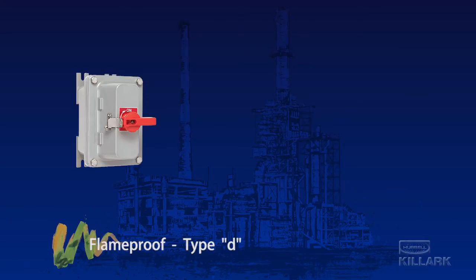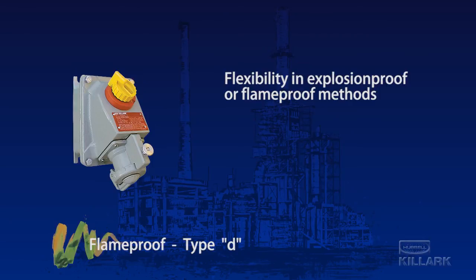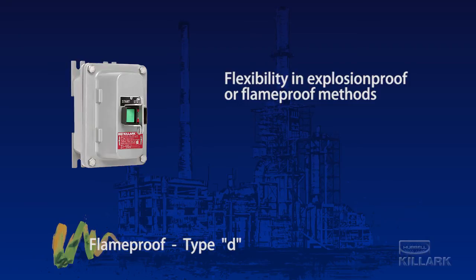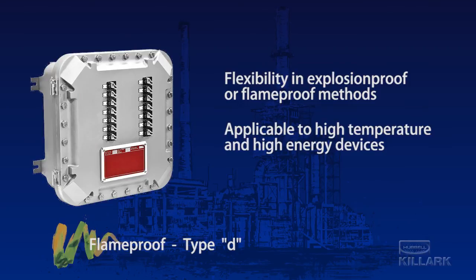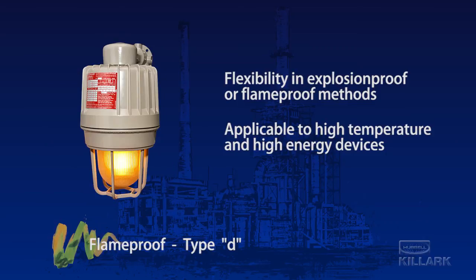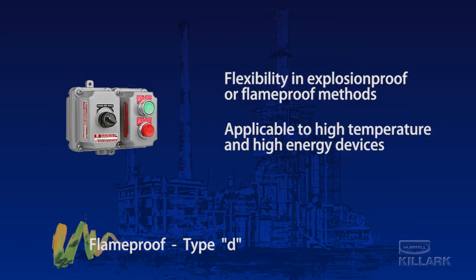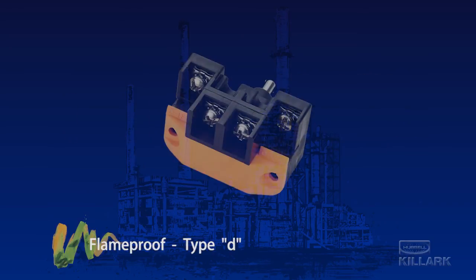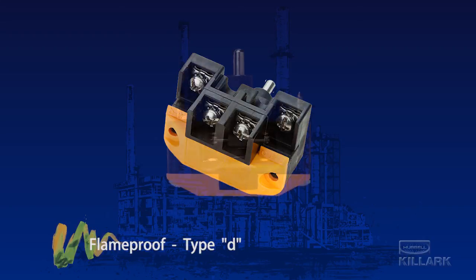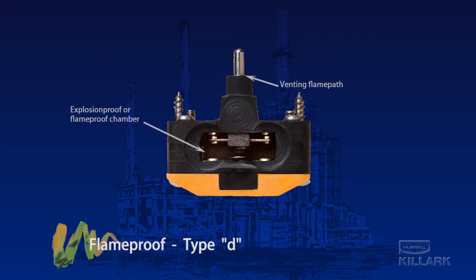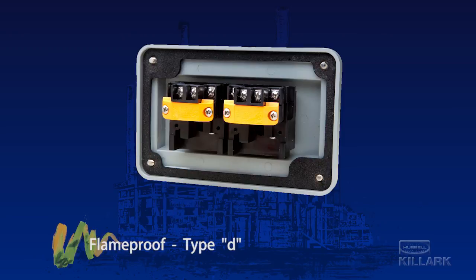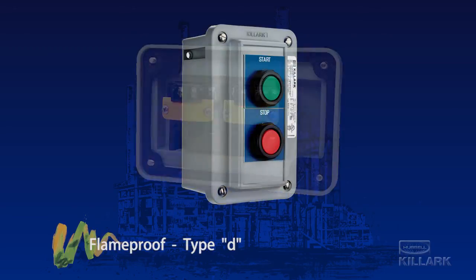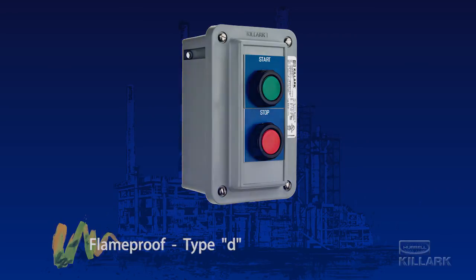Explosion-proof and flame-proof technologies have the flexibility to be applied to a wide range of equipment. This is especially important because it includes high-energy and high-temperature devices where alternative protection methods may be difficult or impossible to implement. The adaptability of flame-proof technology also allows it to be applied at the individual contact level. Enclosing the arcing device in its own miniaturized explosion-proof chamber with a flame path for venting permits a broader range of materials to be used for the fabrication of the overall assembly enclosures.